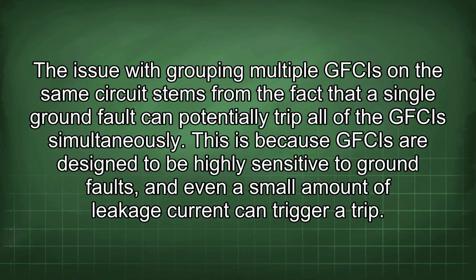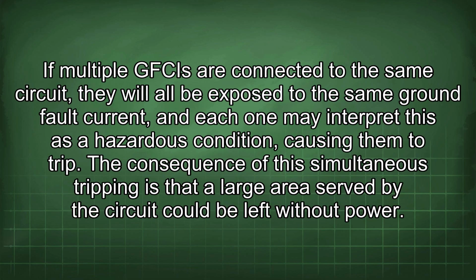The issue with grouping multiple GFCIs on the same circuit stems from the fact that a single ground fault can potentially trip all of the GFCIs simultaneously. This is because GFCIs are designed to be highly sensitive to ground faults, and even a small amount of leakage current can trigger a trip. If multiple GFCIs are connected to the same circuit, they will all be exposed to the same ground fault current, and each one may interpret this as a hazardous condition, causing them to trip. The consequence of this simultaneous tripping is that a large area served by the circuit could be left without power.